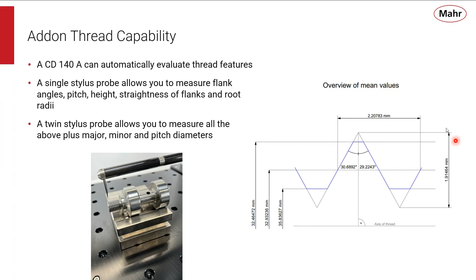So the little brother to the AG machine is the AF machine. It uses all the same probes as the AG. It has all the same software capabilities and additional options that the AG has, like surface finish and measuring threads. The main difference between these two machines comes in the hardware. So the AF has a fixed Z-axis. So there's no adjustment in the Z-axis, and it makes this system ideal if you're measuring the same parts in repetition without needing to move your drive unit around.